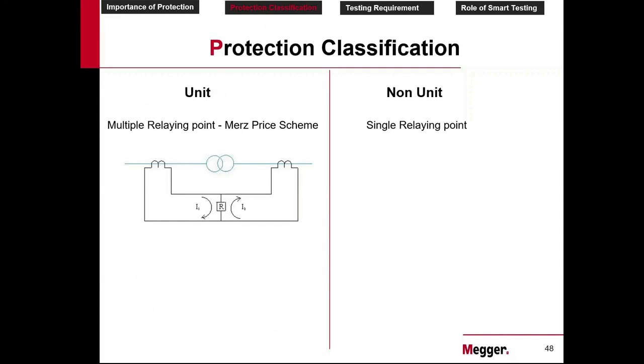This is how it is. So there is an equipment. Here the equipment is a transformer. It can be anything: motor, generator, transmission line, or any equipment in between these CTs. So this black one is your CT, and this is the pilot wire. Any fault occurring here between the CTs will change the direction of the current. So there is a current direction which happens like this. When the current is flowing like this, it will flow in the opposite direction like this.